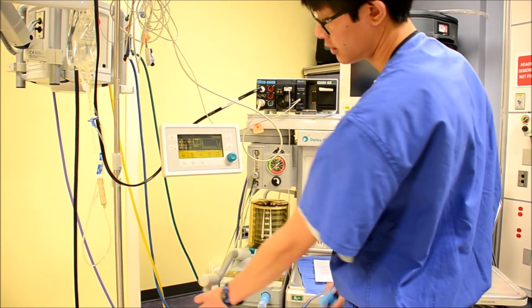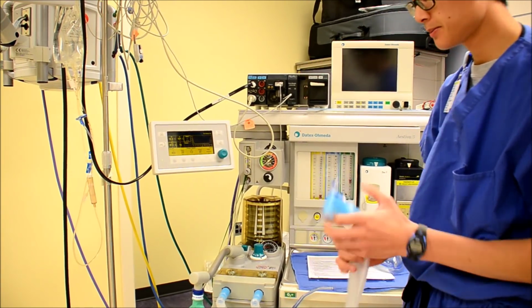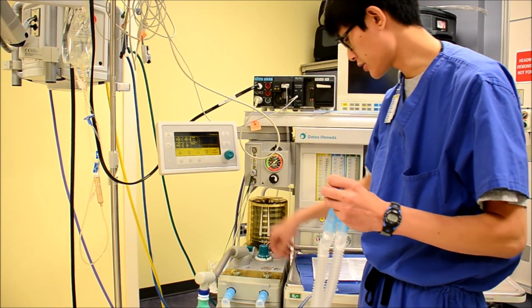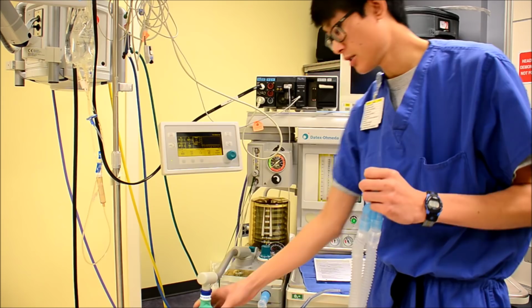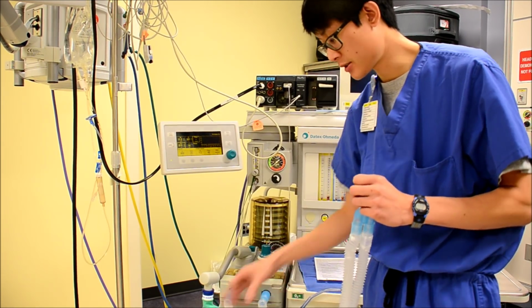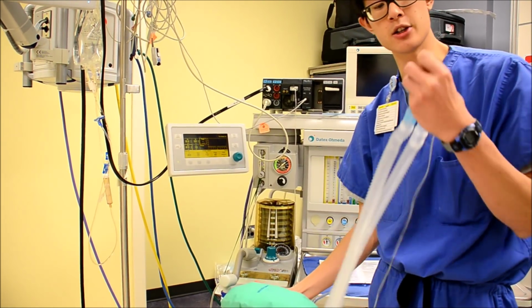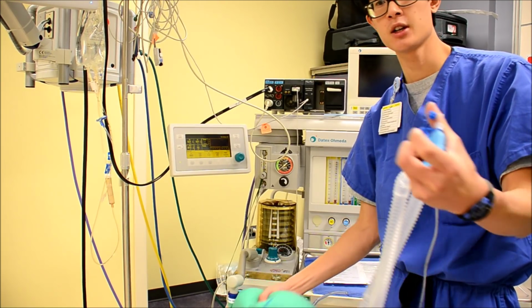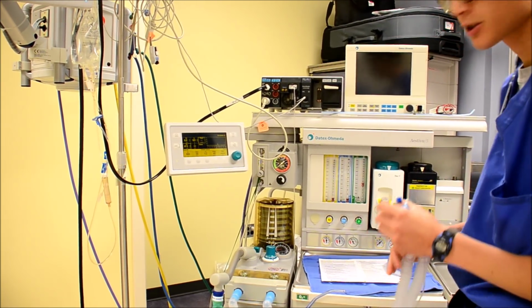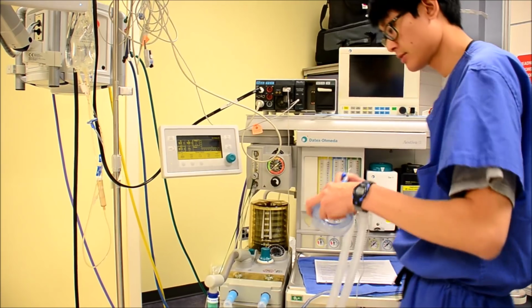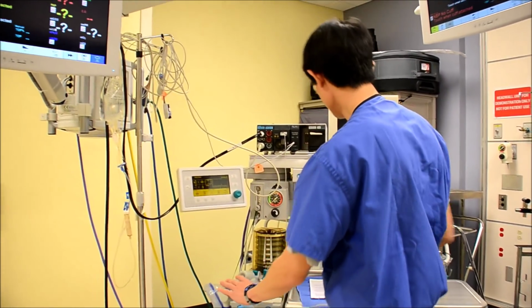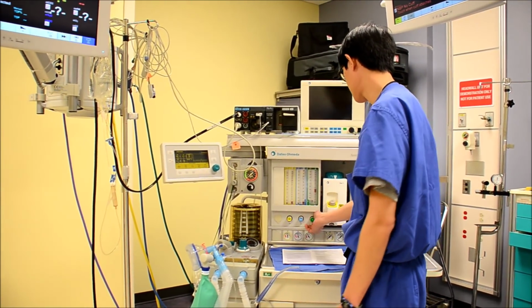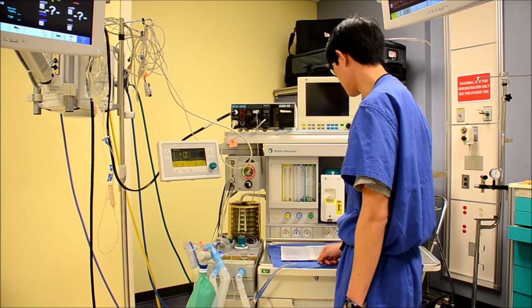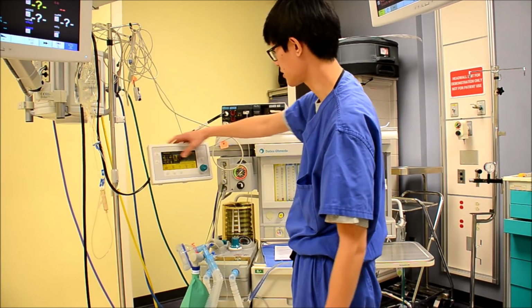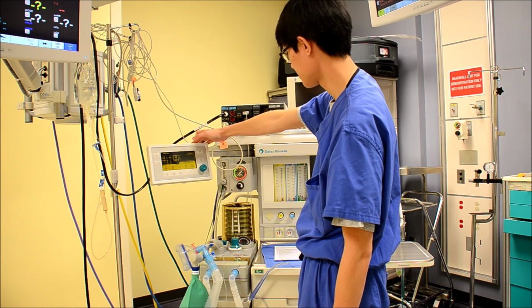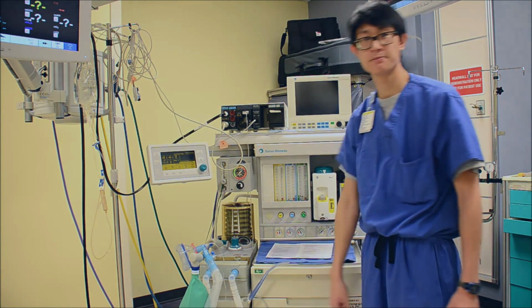So we'll go ahead and connect our bag back to our circuit. Close our APL just a little bit. You flush the O2 flush button to fill our bag, and then you can actually either feel on your face or feel on your hand that you can actually deliver oxygen through the circuit. Connect our mask back. Make sure our vaporizers are off. Turn your flows down to 0, and you can set your ventilator on standby. That's it.